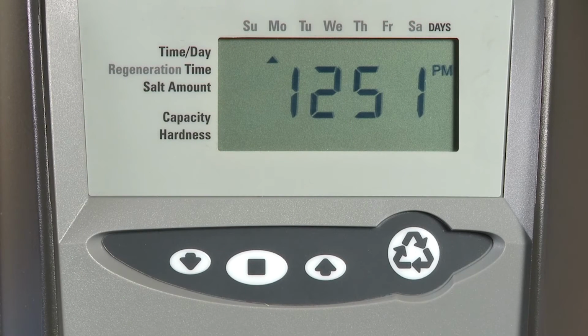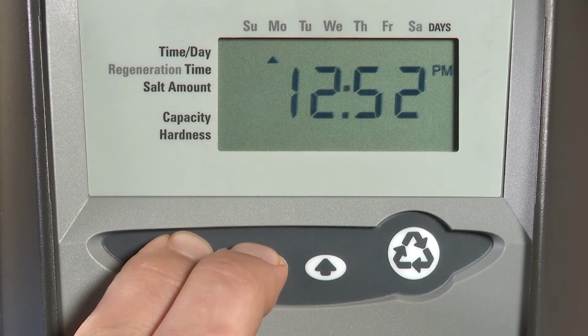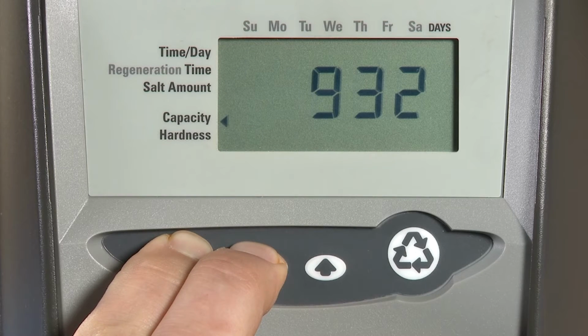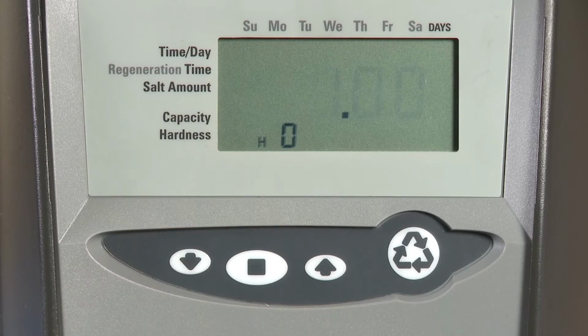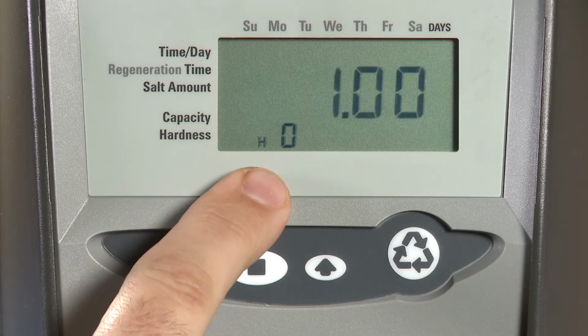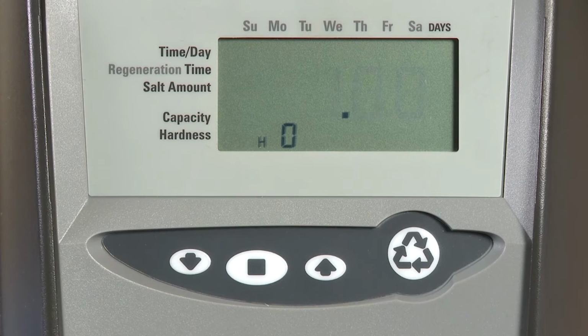Let's now access the history level in Logix controls. To do this, we press the set and the down button and press and hold until the display changes, about 5 seconds. The first item is H0, which is the initial setting of cubic feet or liters of resin capacity.